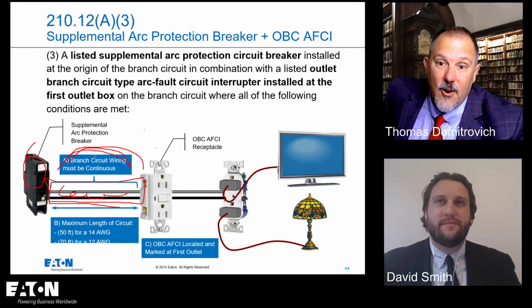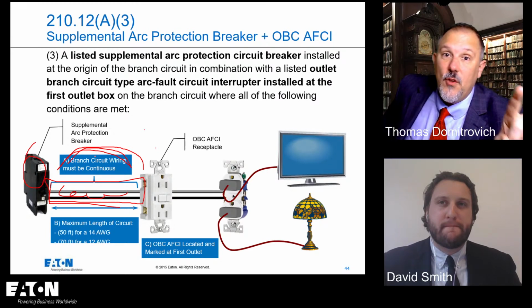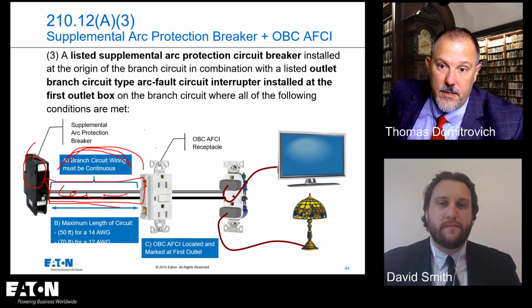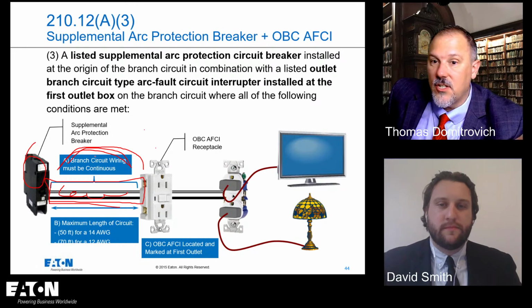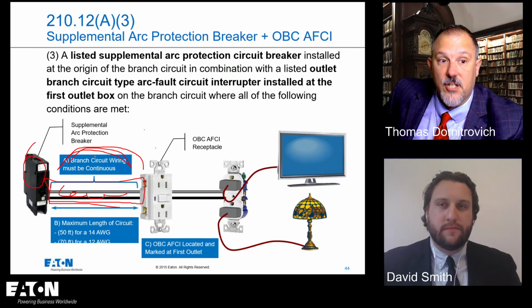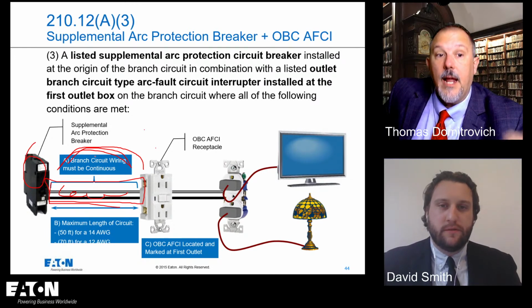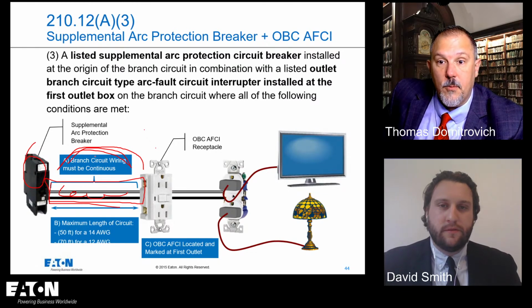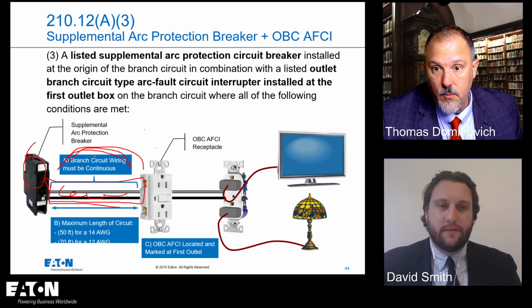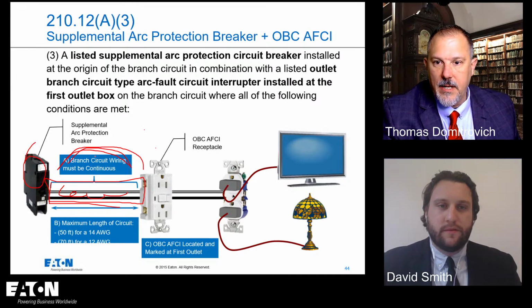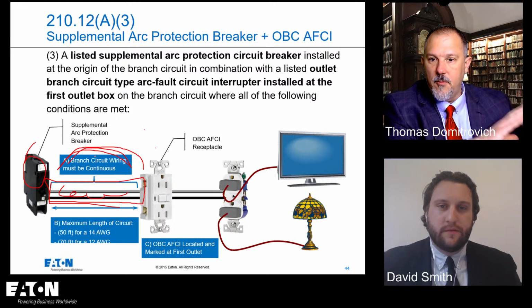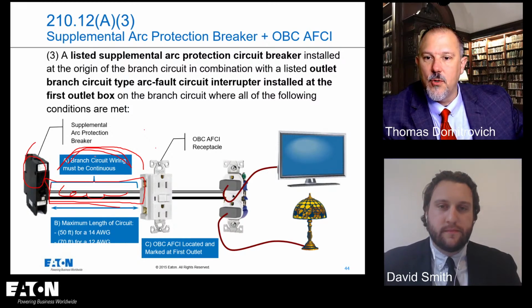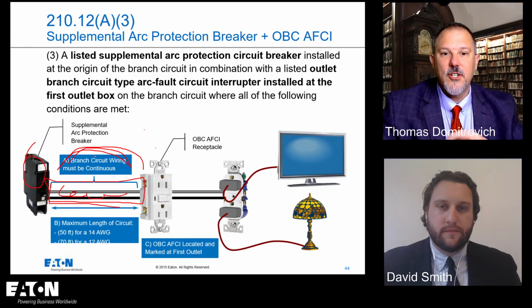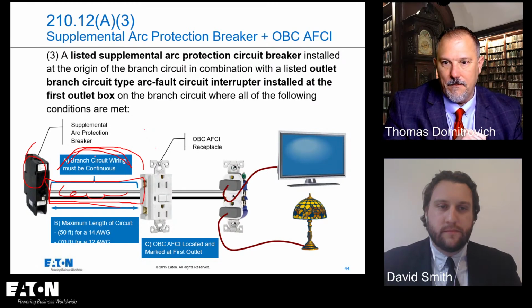Now on the parallel arc, David, they're saying, Tom, if you had a very high available fault current, if you had a parallel arc, it's going to be greater than the instantaneous pickup of that circuit breaker. Sure. And that's going to trip the thermomagnetic circuit breaker. So what they wanted to do was say, look, put an OBC downstream of a thermomagnetic circuit breaker, and the thermomag breaker will take off the short circuit current if there's a parallel arc fault. And the OBC looks at series arcs and gives you complete protection downstream.